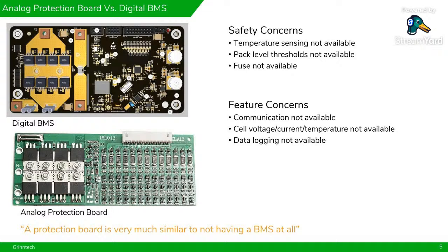That's why it's not recommended to use this type of protection board - always use a proper BMS. Of course there's a price difference between the two, but it's not very high, not more than 15-20% maybe. It's not a huge difference in price, but it's definitely important from a design point of view. Designing the bottom one is very easy; designing the top one is not. There are very few companies in India, or worldwide, who can design a proper BMS with all the safety features. That's why you see frequent use of the analog protection board - making it is easy, but it's not safe.